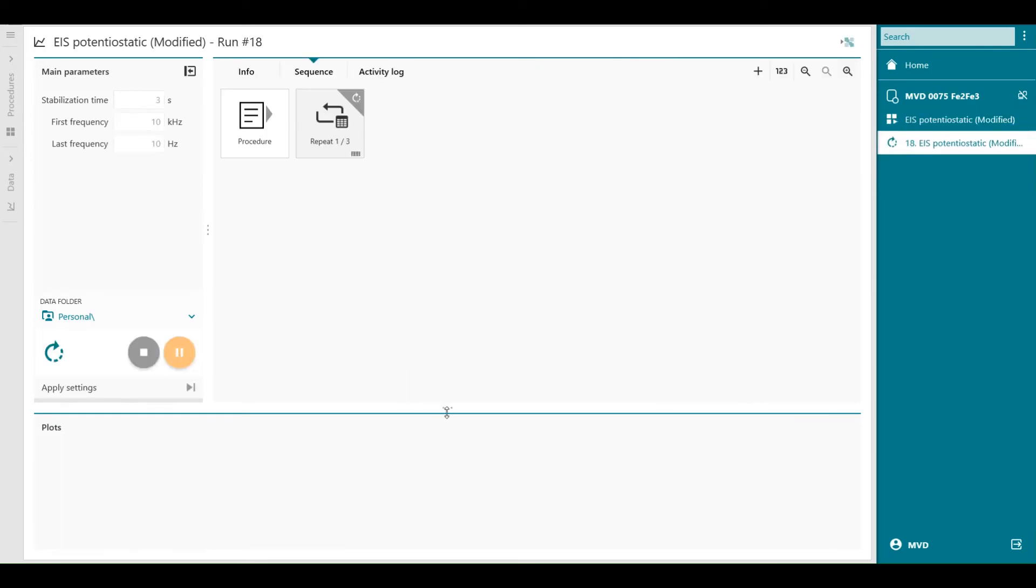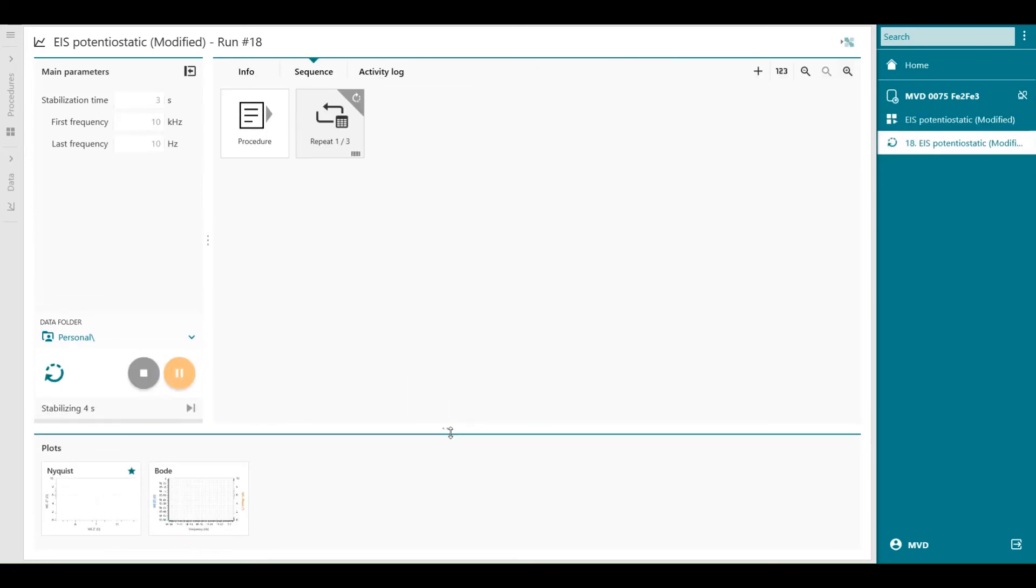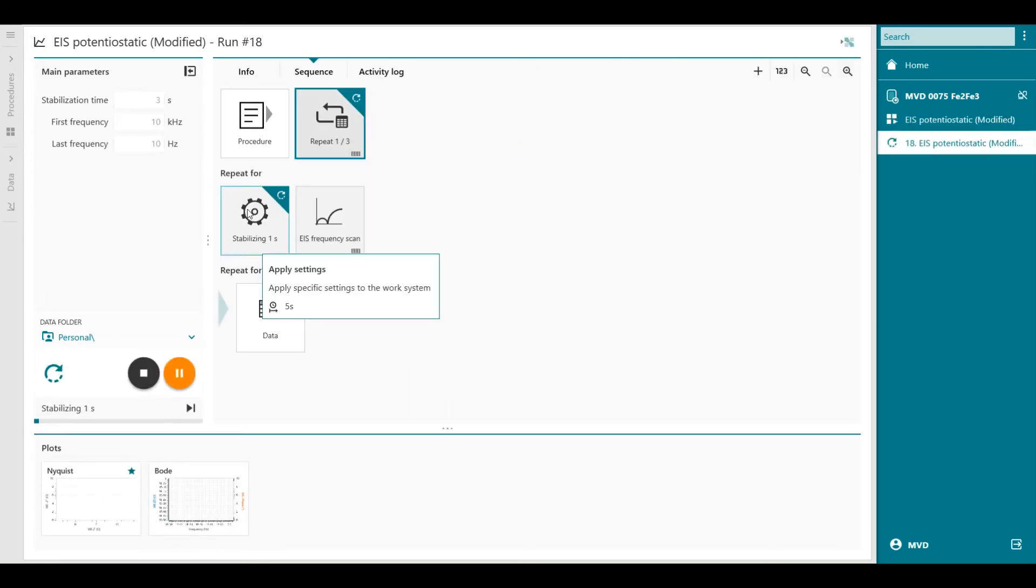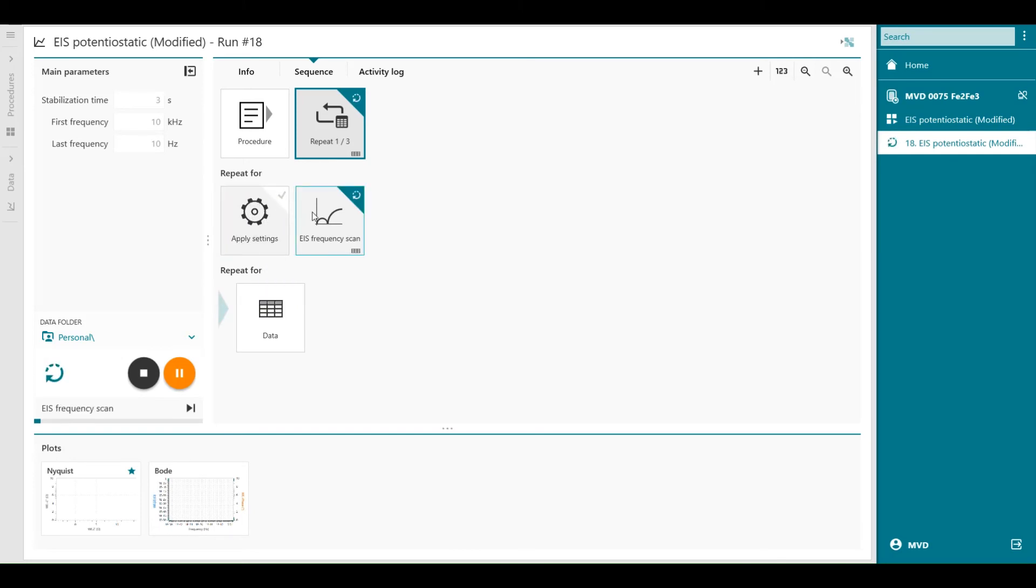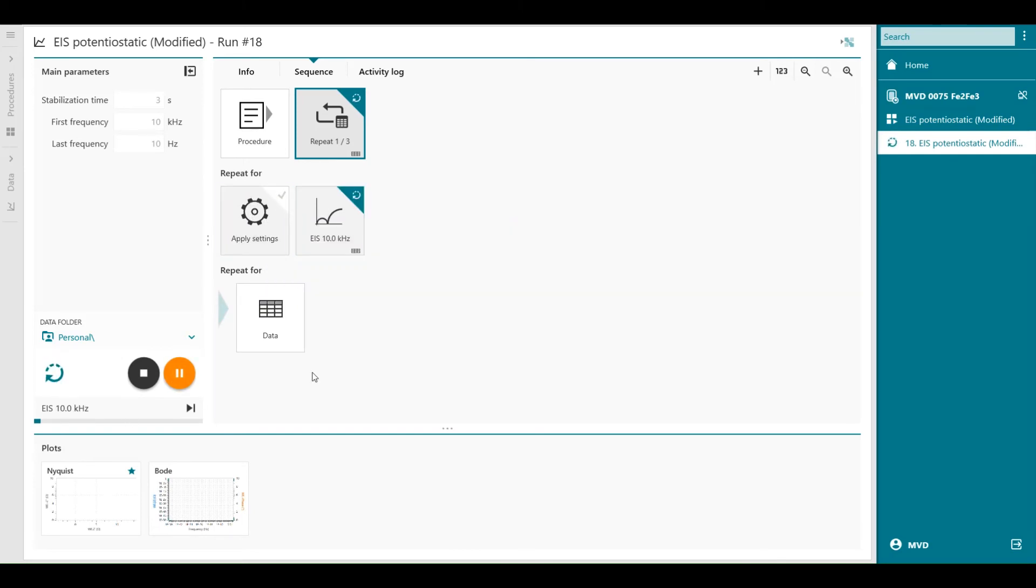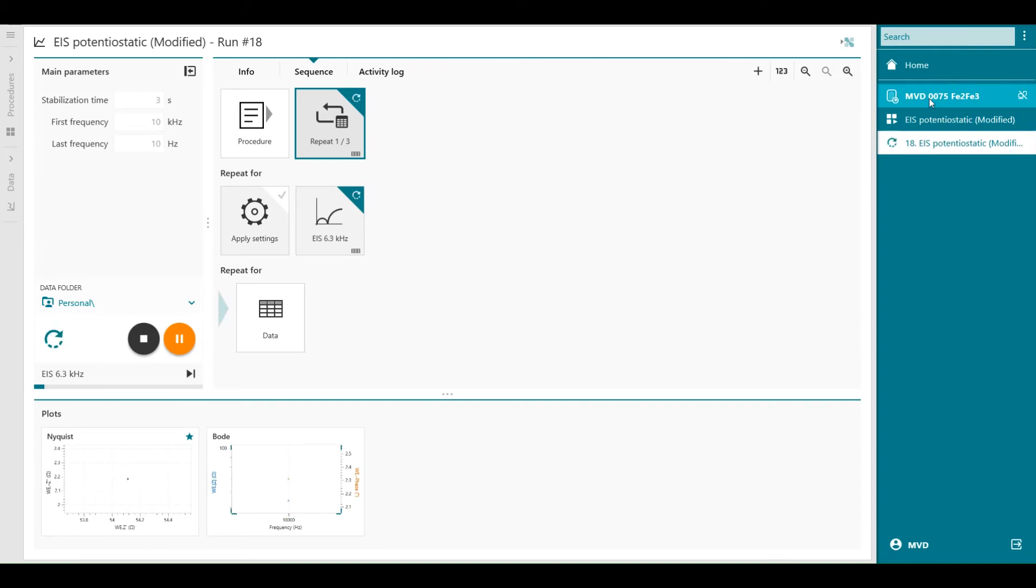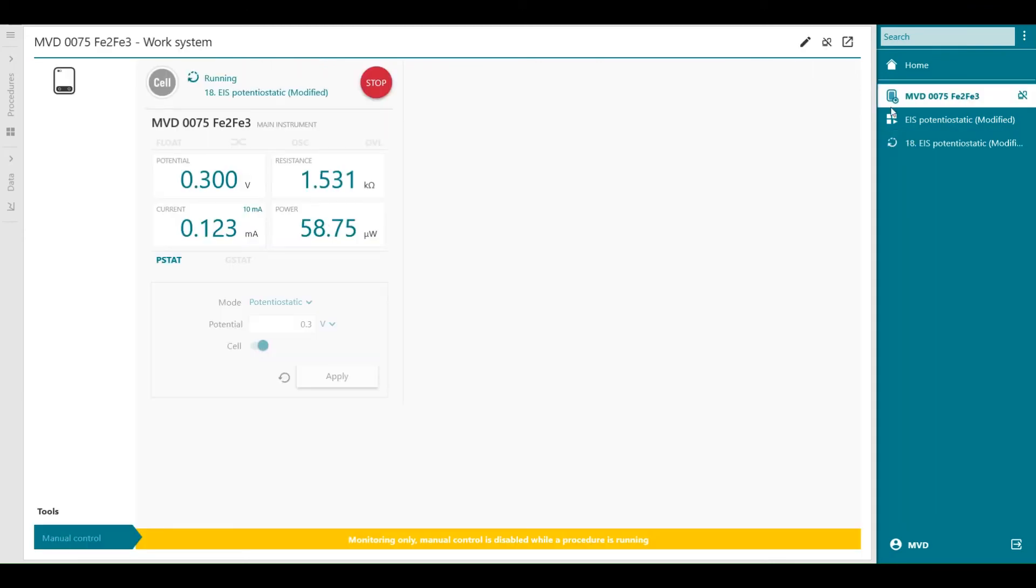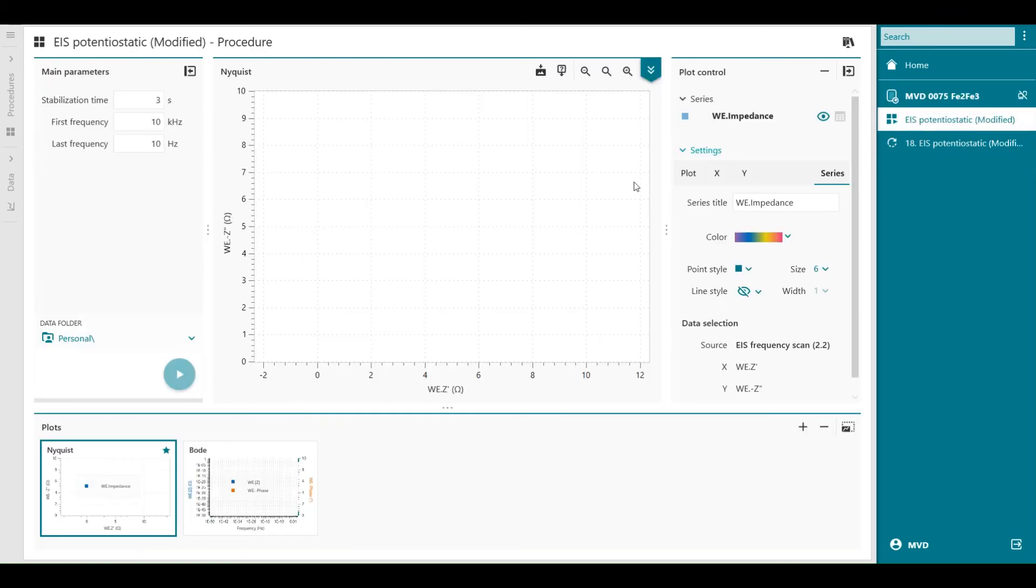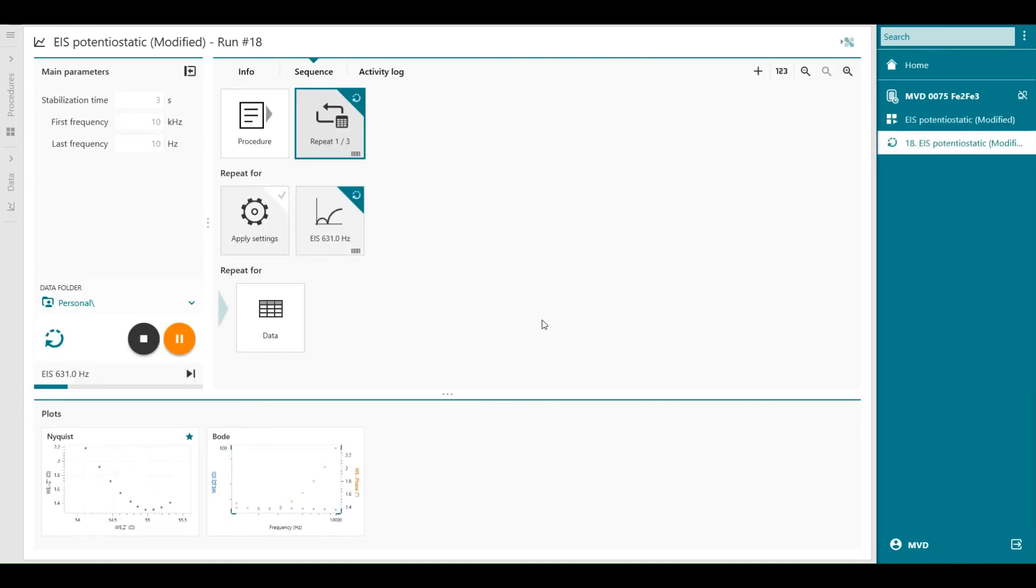The measurement starts. The first repeat is applied and you can see in which command it is. It's the stabilization phase. Then it's in the impedance measurement. So we can follow what kind of frequencies. And also you can see in the vionic in the upper right corner. You can see that we are applying a 0.3 volts DC voltage.